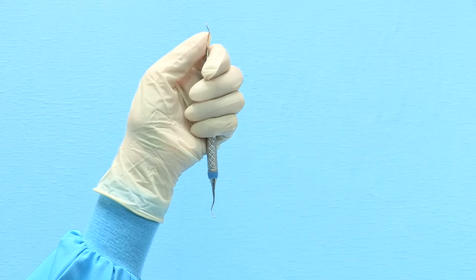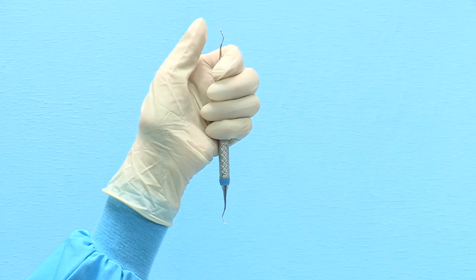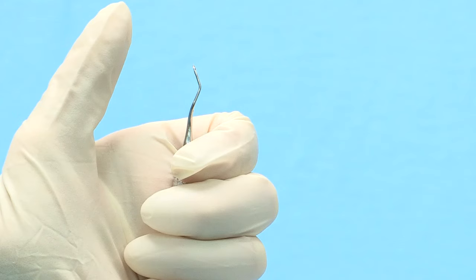To sharpen a Gracey curette, begin with the odd-numbered end of the curette. Hold the instrument vertically in your non-dominant hand with the toe pointed toward you. Use a firm palm grasp and brace the top shank of the instrument with your thumb.